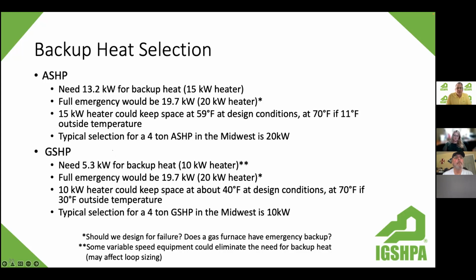When we look at geothermal, here's where we can have some pretty big impact. I have a slide coming up that shows wire size and breaker size, and even our electrical panel, which could be affected. If we wanted to, we could go with 5.3, but again, we're probably going to need to go to 10 kW. That's the typical size available from most manufacturers. Again, 20 kW if we wanted full emergency. That's not typical on geothermal. Where we see that a lot on air source, at least from my experience in the Midwestern part of the US, it's not typical to have full backup on geothermal.